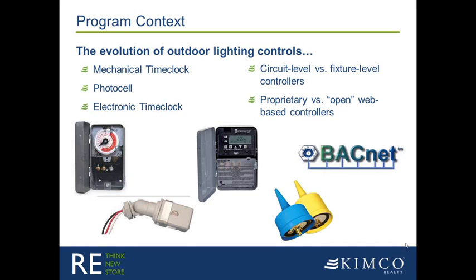Over on the left-hand side, there are a couple of categorical classes I'd like to mention. Lighting controls can be installed for either circuit-level control or fixture-level control. Most are wired for circuit-level control, meaning that any time you turn something on and off, you are controlling a group of anywhere from 2 to 10 fixtures or light poles — more than that for building lights such as canopy lights or wall packs. In terms of parking lot poles, probably around 4 to 6 poles per circuit. Circuit-level is much more common, and the benefit is you have much fewer components to install, but much less granularity of control.